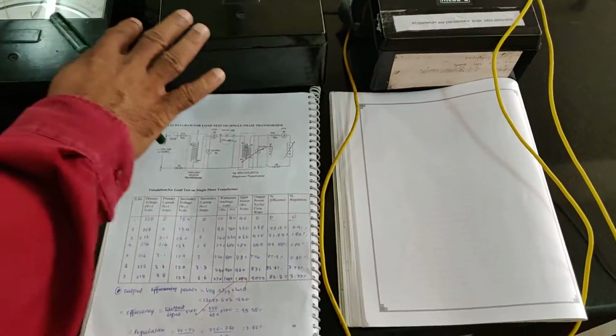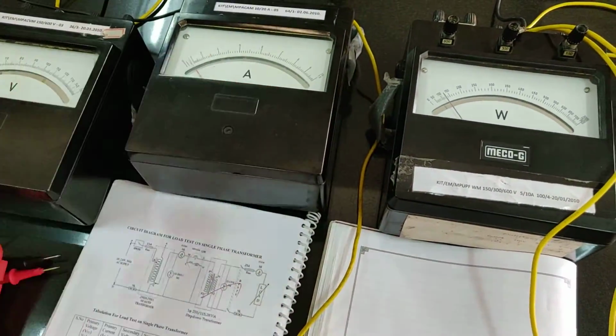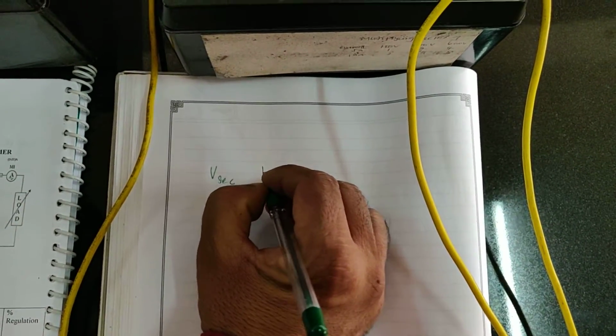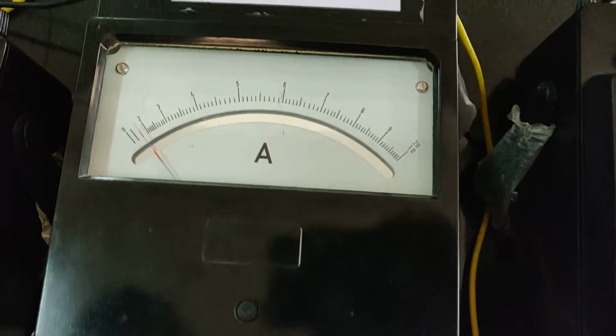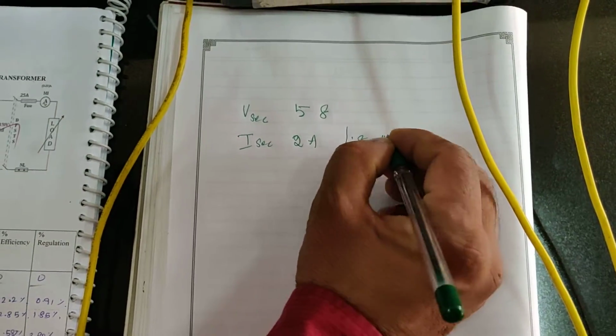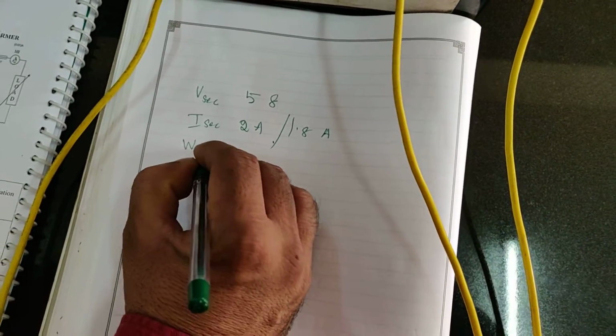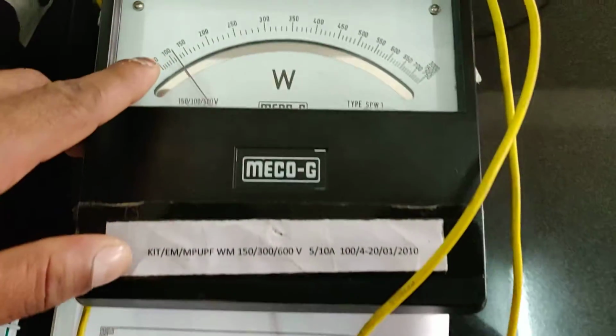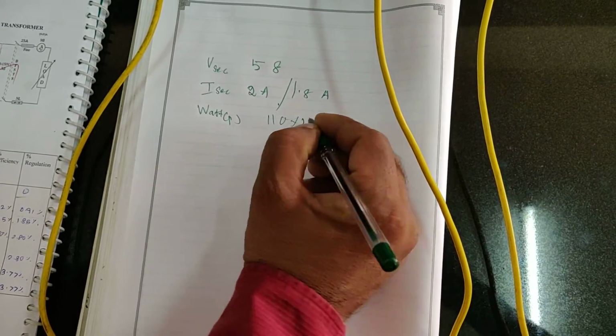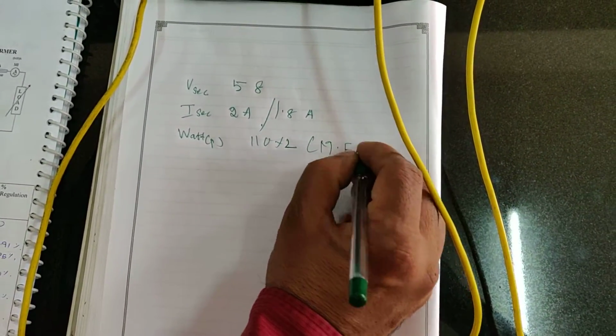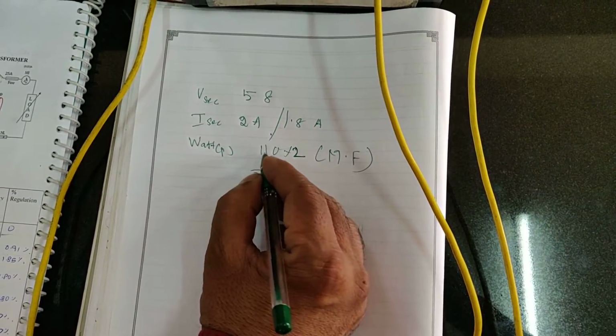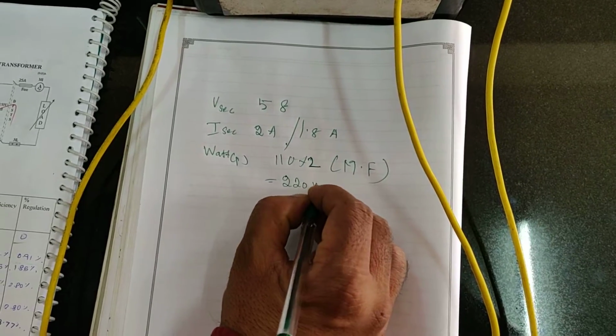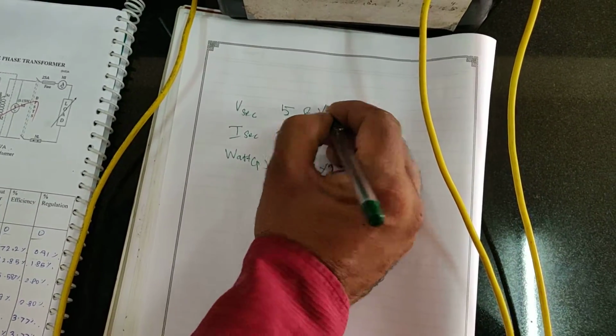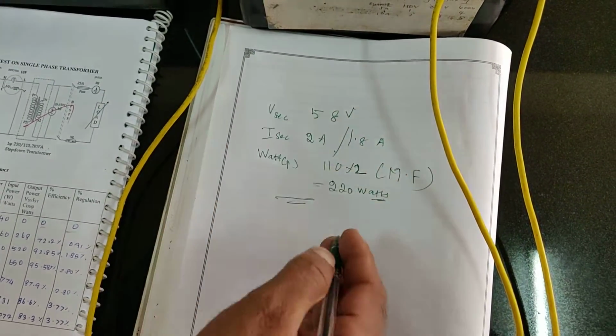Let me show you practically how it is consuming 300, and prove it for one reading. Let the primary voltage be V, secondary voltage is 58, and the secondary current is approximately 2 amperes, say 1.8 amperes. The wattmeter reading, that is power, is 110 into 2, because this 2 indicates the multiplication factor, so 110 into 2 is 220 watts.